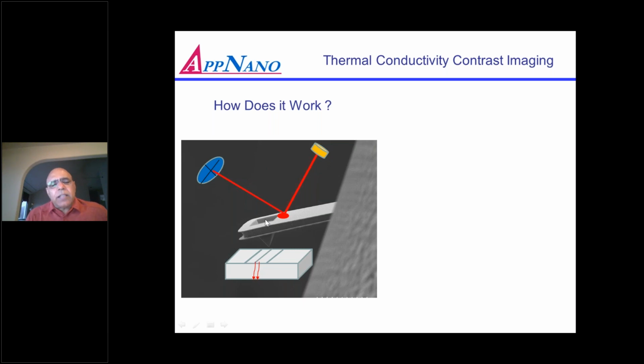Normally we don't take this precaution when we are using the probe for topography or other applications, but here it is important, because if you want to measure temperature, you don't want to influence the thermocouple with the laser heating. Normally the laser used for most AFM is about 1 milliwatt, and 1 milliwatt can raise the temperature by up to about 100 degrees Celsius. So just be careful. Depending upon how you focus, the temperature can be less or more, but one can easily get a 10 to 20 degree temperature increase when you have the laser on the thermocouple.